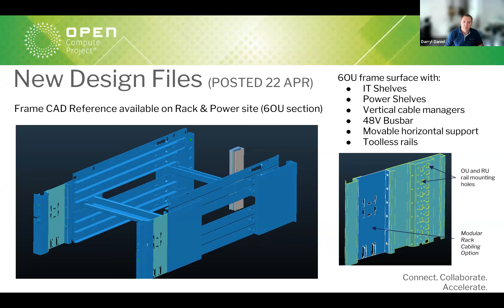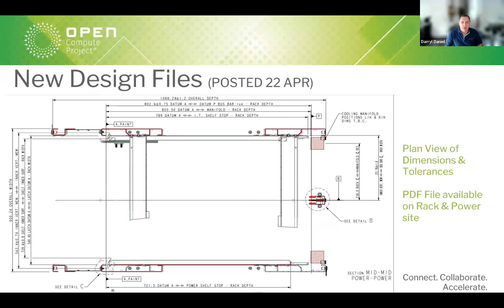Similarly on the V3 wiki page, we're also including a 2D PDF drawing with a cross section of the rack, which provides some of the relevant dimensions and tolerances for the primary interfaces. The datum that's referenced in the drawing is where your latches for your IT gear would clip into. The rest of the interfaces to the bus bar, the manifolds, and the hard stops for the IT gear are all referenced off of that primary datum. So again, I invite everyone to check out the V3 OCP wiki page, and these files are available for you to download as needed.